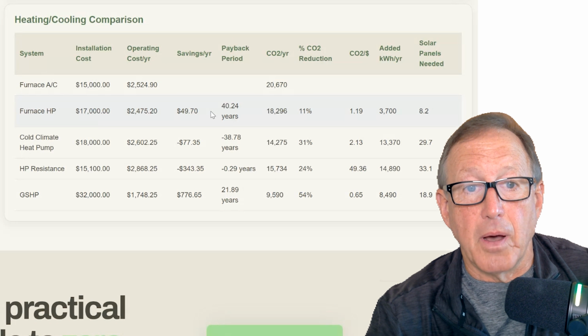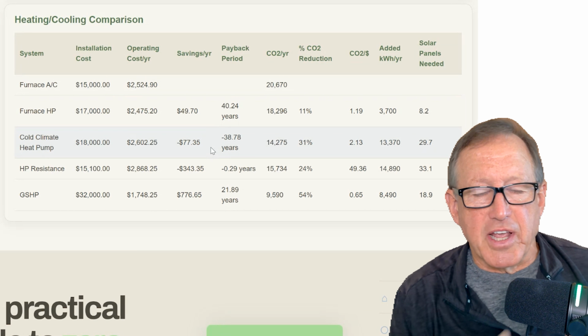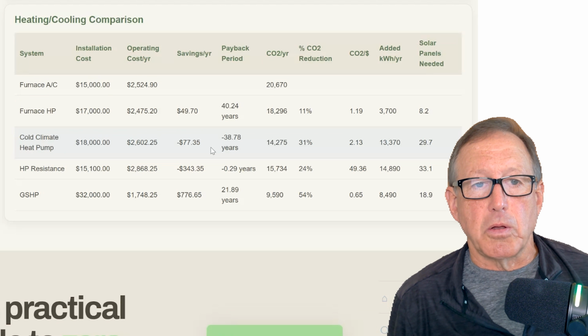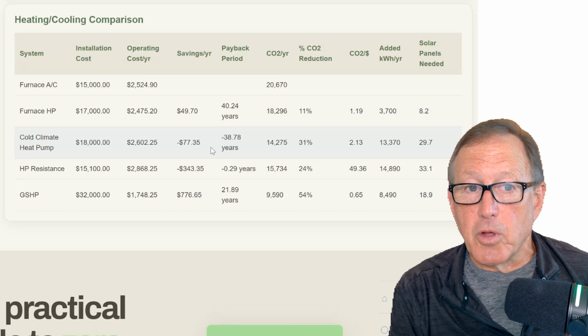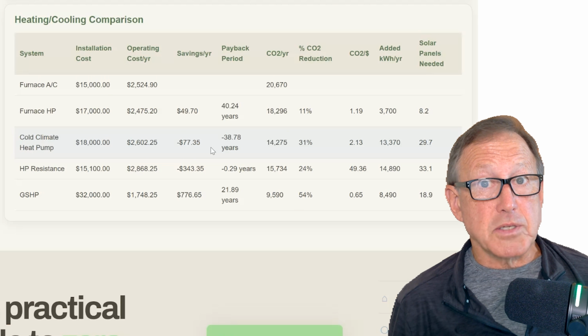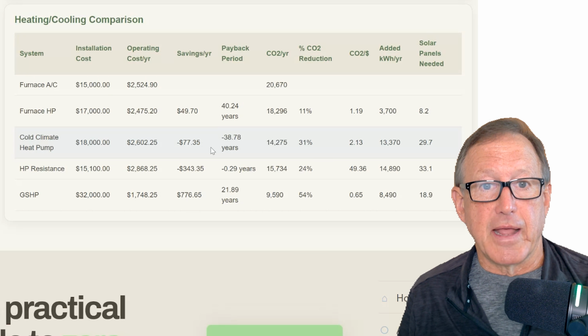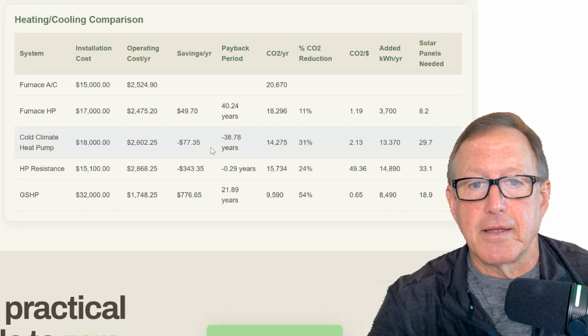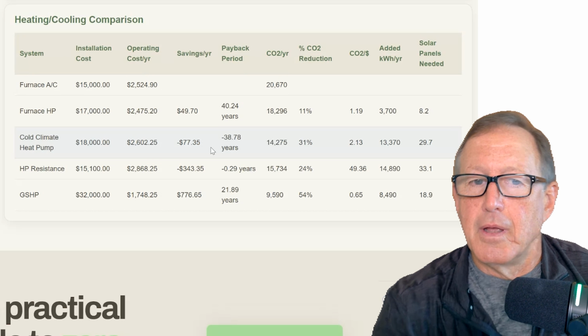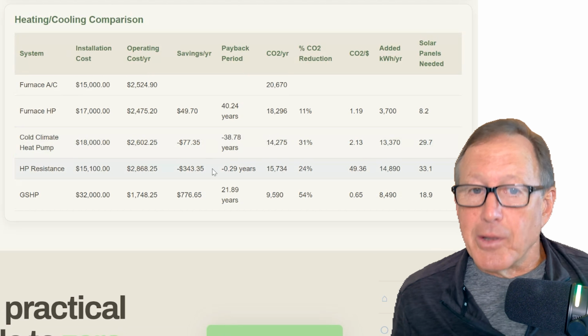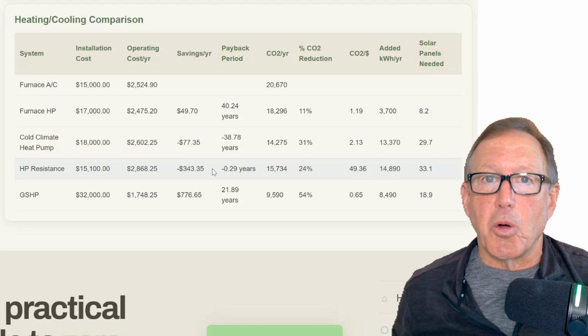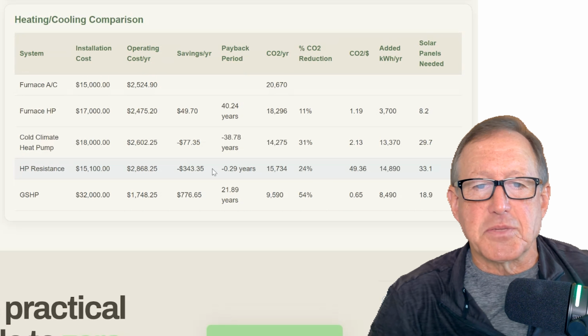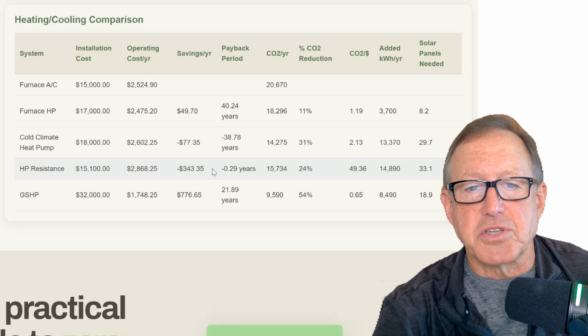The cold climate heat pump actually costs you more because at really cold temperatures it still works, but it's more expensive than natural gas. The resistive heat doesn't look good at all because it's cold a lot of the time and you're using that expensive auxiliary heat.